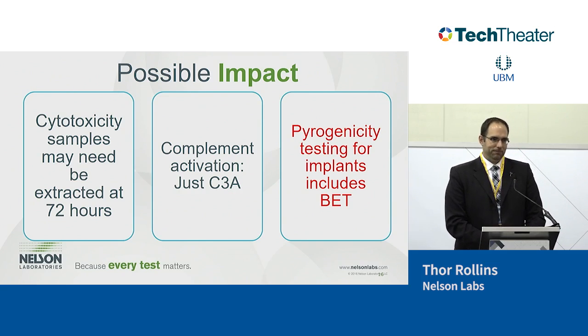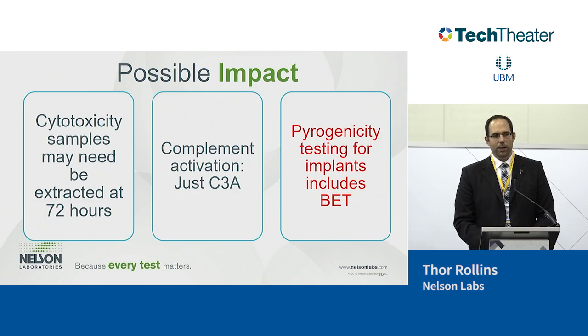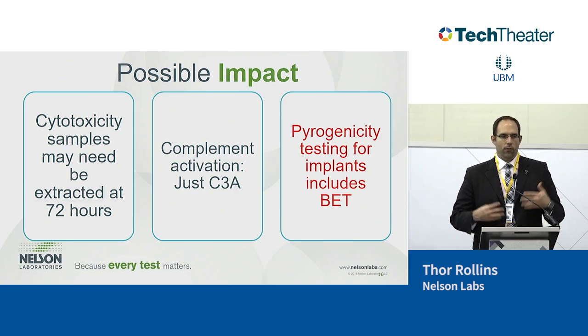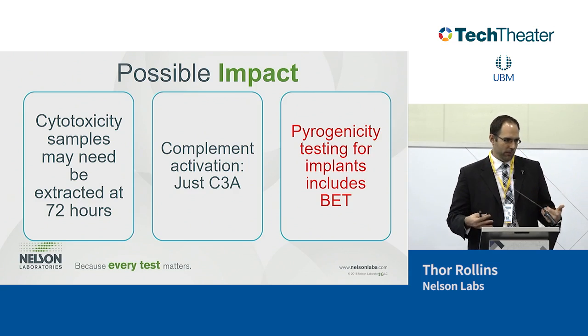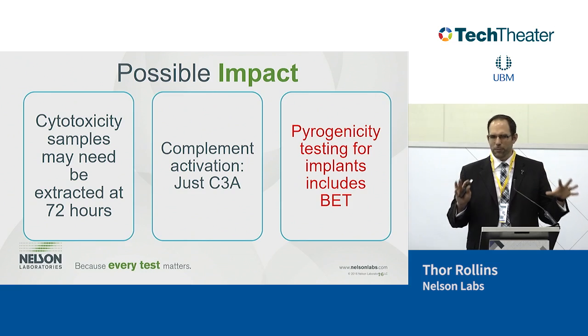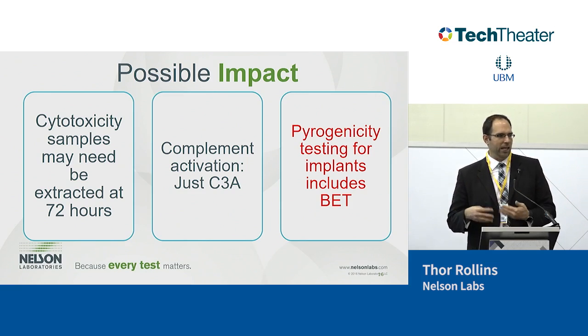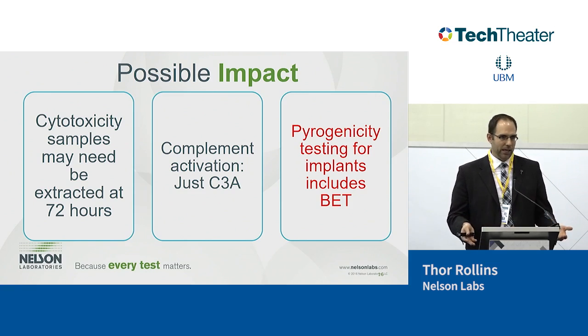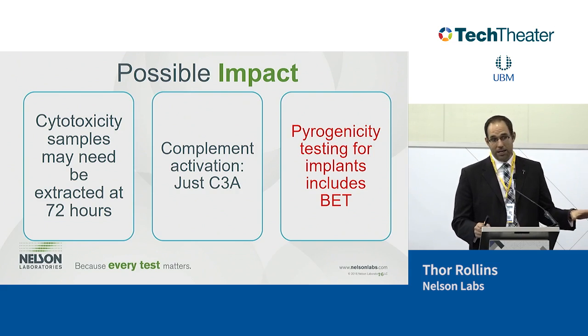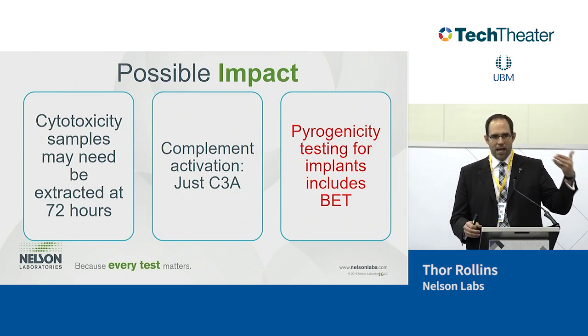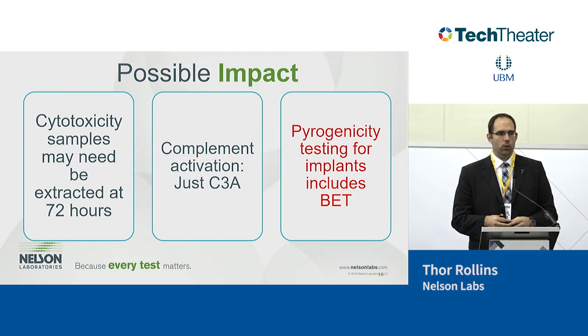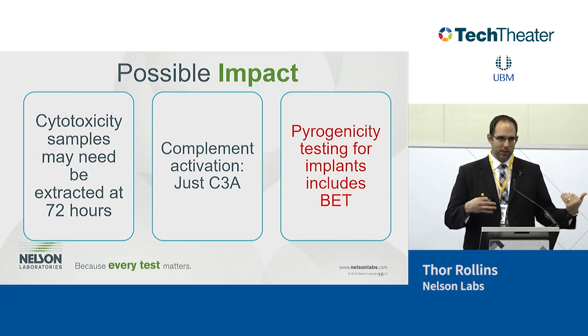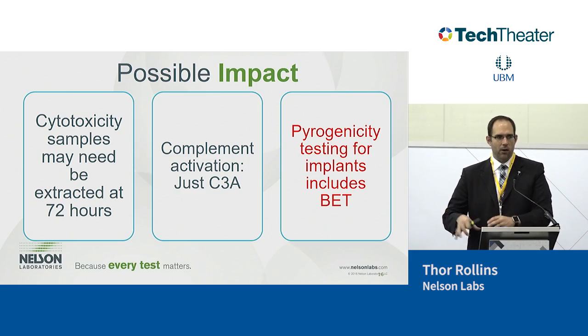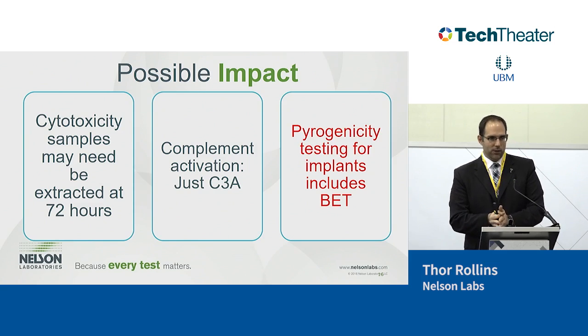Then we have pyrogenicity. This endpoint has been a little bit of an issue going forward for the FDA. So for those of you that don't know, a pyrogen is something that causes a fever, okay? So there are two types of pyrogen tests we run. We run something called a bacterial endotoxin test, or BET, sometimes called an LAL test. That looks for something called endotoxin, which is in gram-negative bacteria. It's only in gram-negative bacteria, and so we have to screen for that type of endotoxin. And we do that by using horseshoe crab serum, which is a kind of cool test. If you want to come to Nelson Labs and see us run it, we don't actually have horseshoe crabs running around, but we have their serum, which is kind of cool. So you can come and check it out. But we have to run this test looking for that specific bacterial endotoxin.